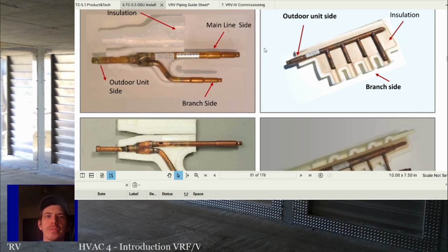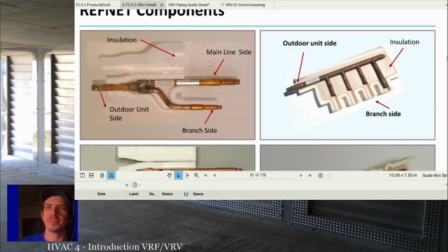Part of the magic of these VRF systems is the ability to serve multiple indoor units off a set of outdoor units with a single set of two or three pipes. Part of how that can happen is installing these Y kits to split the pipe, installing them properly, and using the ones that are required for whatever situation you're in. And these things are kind of funky, all right? But they work pretty well. But there's some rules you have to follow when you install those, and we'll look at those piping rules.